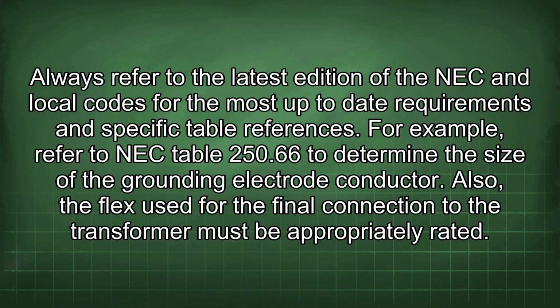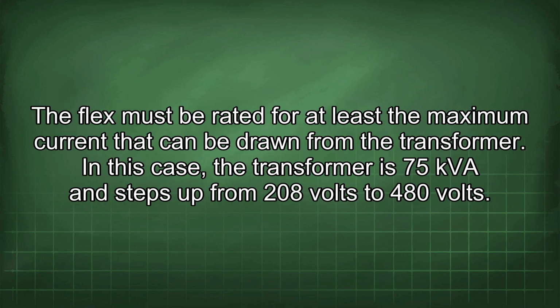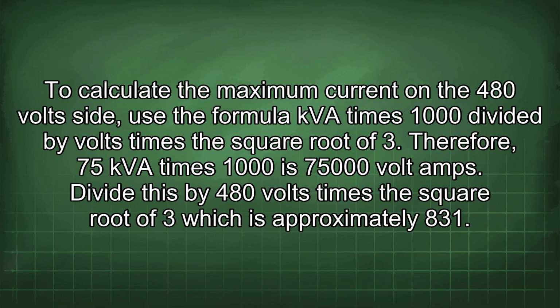Also, the flex used for the final connection to the transformer must be appropriately rated. The flex must be rated for at least the maximum current that can be drawn from the transformer. In this case, the transformer is 75 kVA and steps up from 208 volts to 480 volts. To calculate the maximum current in the 480 volts side, use the formula kVA times 1000 divided by volts times the square root of 3.